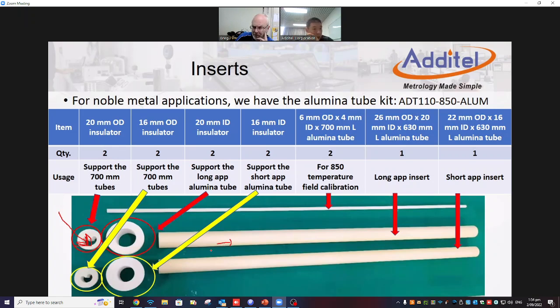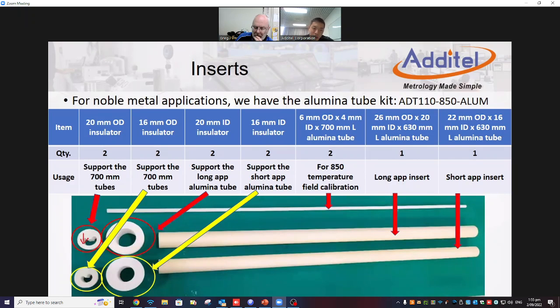So this is the alumina tube kit. When we do the testing, normally for noble metal testing we would only test one DUT at a time - one reference and one DUT. We have two holes right here, or one hole for two probes, which is good enough. If they have three probes, no problem - they just need to put this little thing upside down, then we have probe 2 and probe 3 staying together.